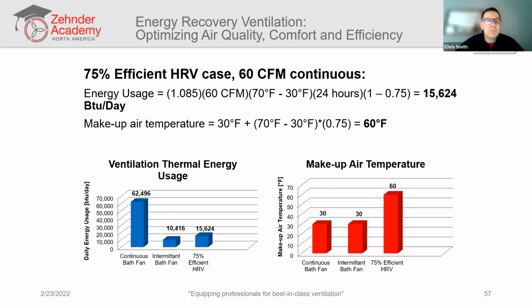So if we look at the column on the left and the column on the right, we're looking at the same ventilation rate. So our indoor air quality profiles would look the same, but our energy usage and our comfort levels are very different. We're using way less energy with the HRV. And on the right, we see that our makeup air temperature at 75% efficiency is going to be 60 degrees. So that's double the temperature of the incoming air using a bath fan only.